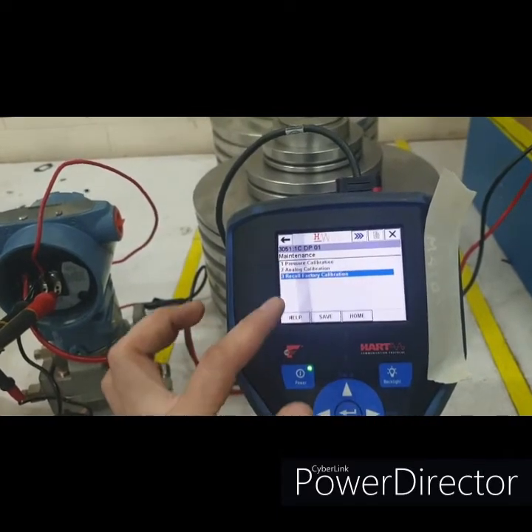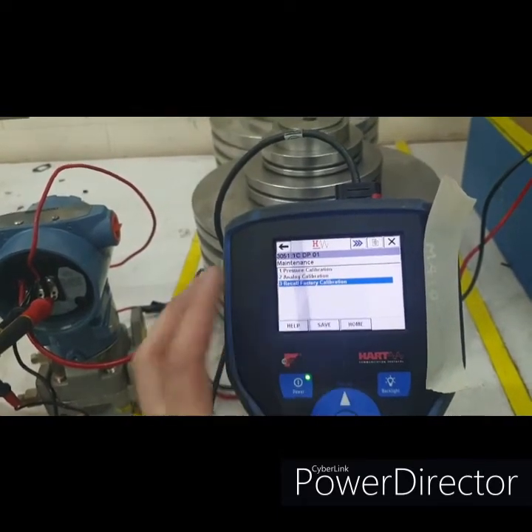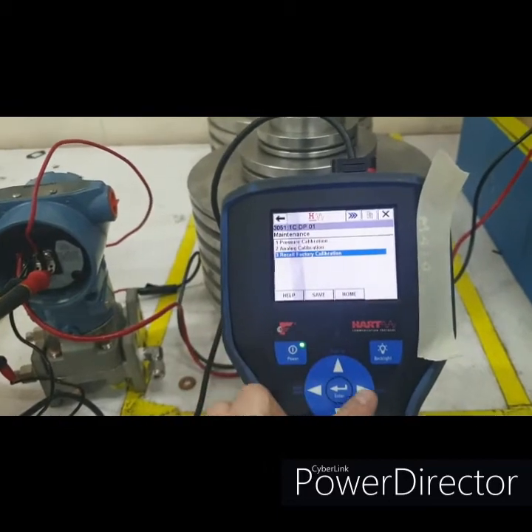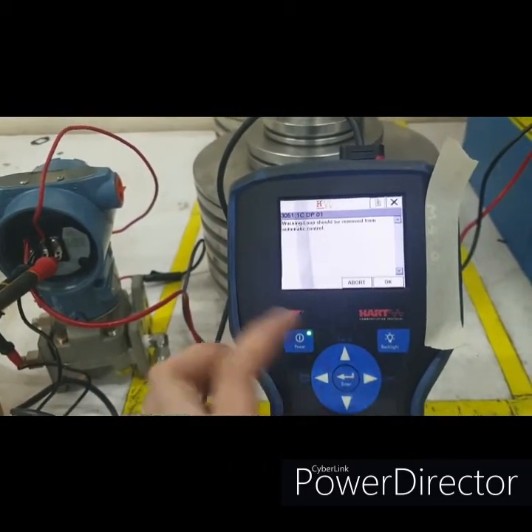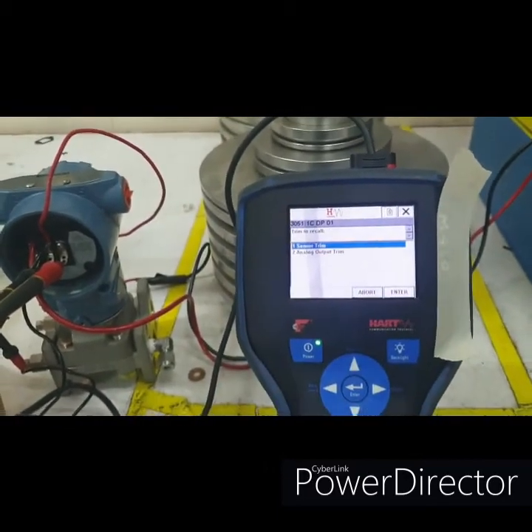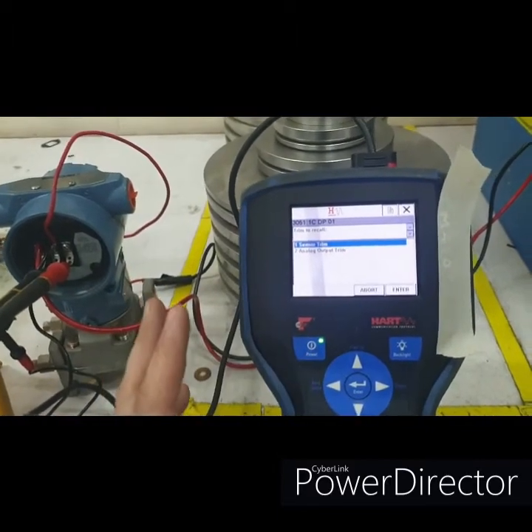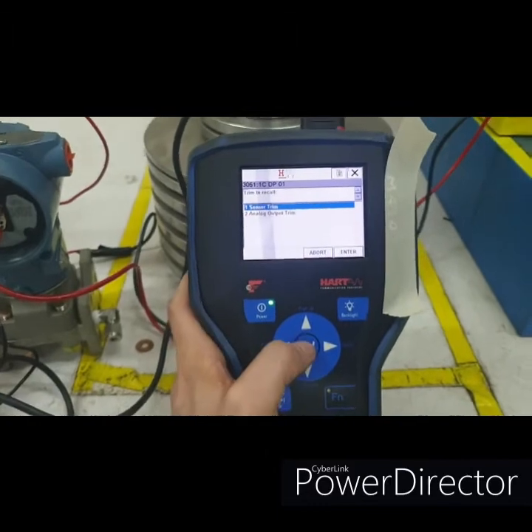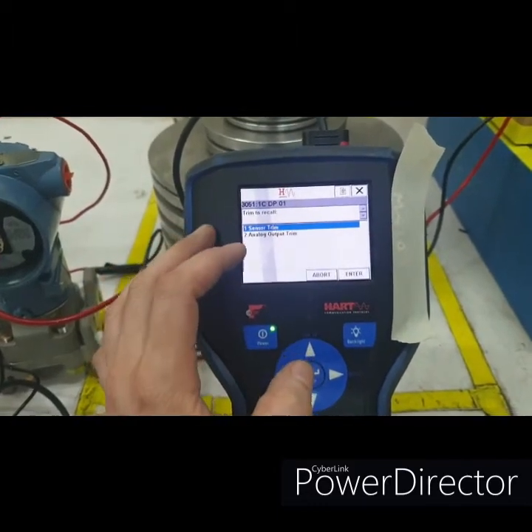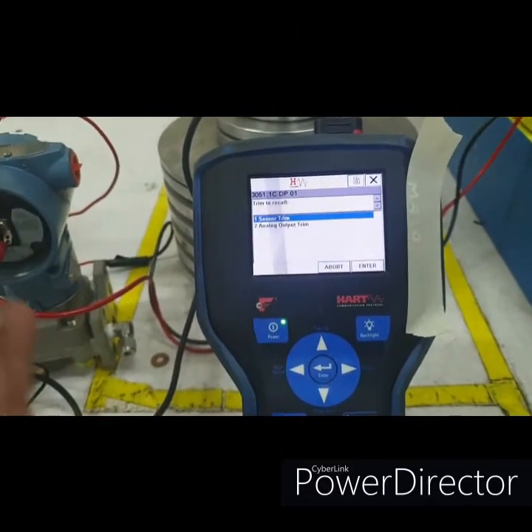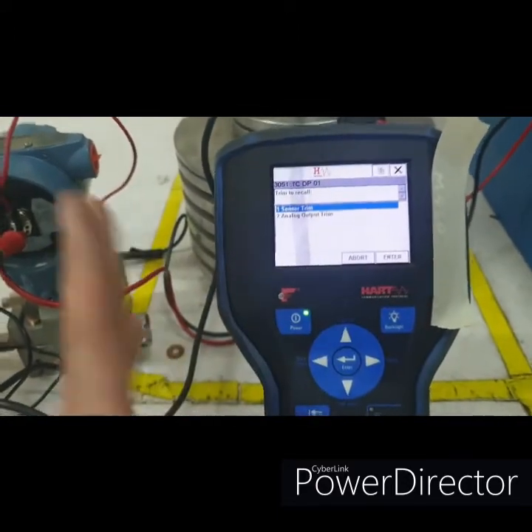Then go to recall factory calibration. So it will go back to the default values. If we have done sensor trimming or analog output trimming, it will go back to the default settings. Restoration of trim values complete.